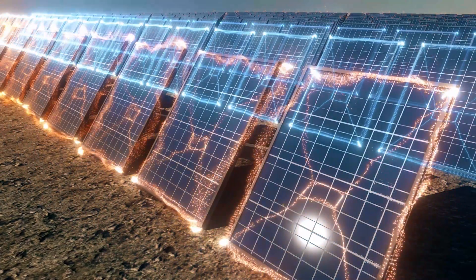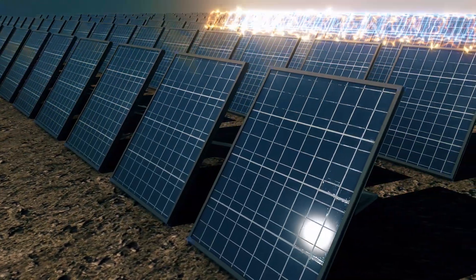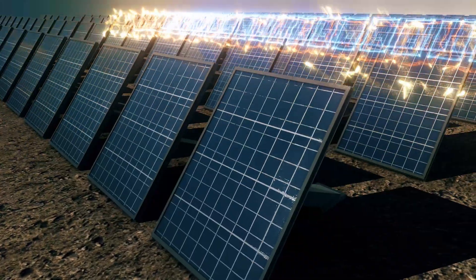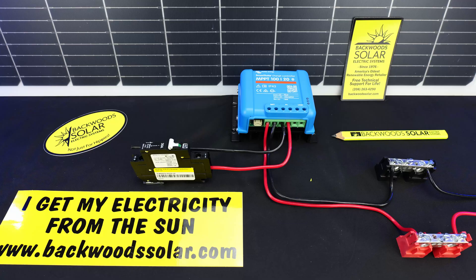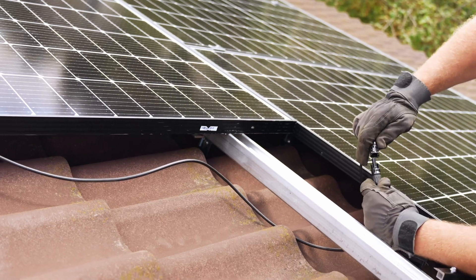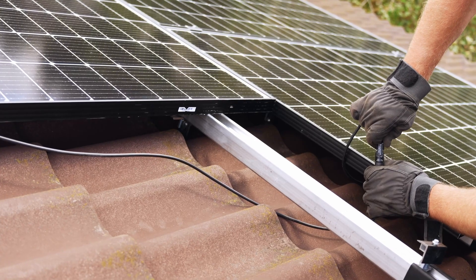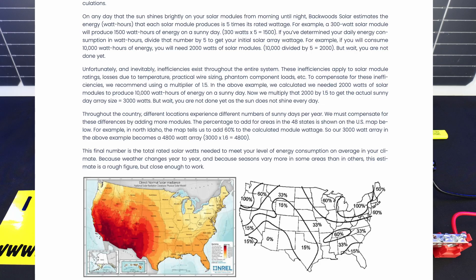This number assumes 100% efficiency, which doesn't happen in the real world. So if we take that 2,000 watts, we're going to use a 1.5 multiplier for expected efficiency losses. This would be wire losses, cabling, equipment, and so on. So using that 2,000 watts with our efficiency loss, we now need a 3,000 watt array to produce that 10,000 watt hours or 10 kilowatt hours.